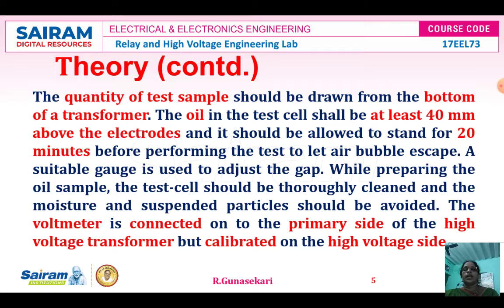A suitable gauge is used to adjust the gap between the electrodes. While preparing the oil sample, the test cell should be thoroughly cleaned, and moisture and suspended particles should be avoided. The voltmeter is connected to the primary side of the high voltage transformer but calibrated on the high voltage side.